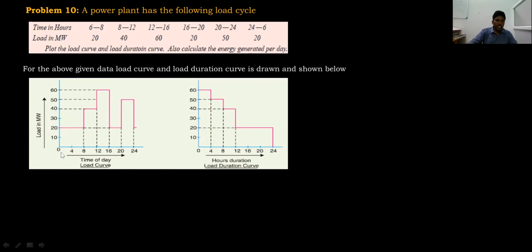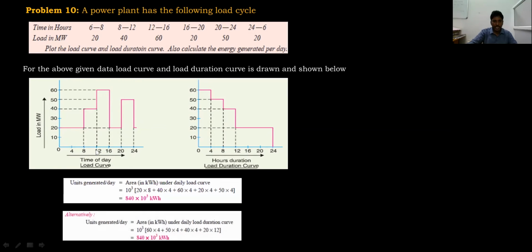For this one, from 0 to 8 hours, the load is 20. So 8 into 20, plus 4 into 40 for 8 to 12. In the same way we need to find all these areas, and finally if you add all these things, we get the area under the curve, that is the number of units generated. If I find the area of the load duration curve, the value will be the same. Units generated per day, if I calculate from the load curve, is 840 into 10 power 3 units. In the same way, for the load duration curve, the area is 840 into 10 power 3 kilowatt hours, the same thing.